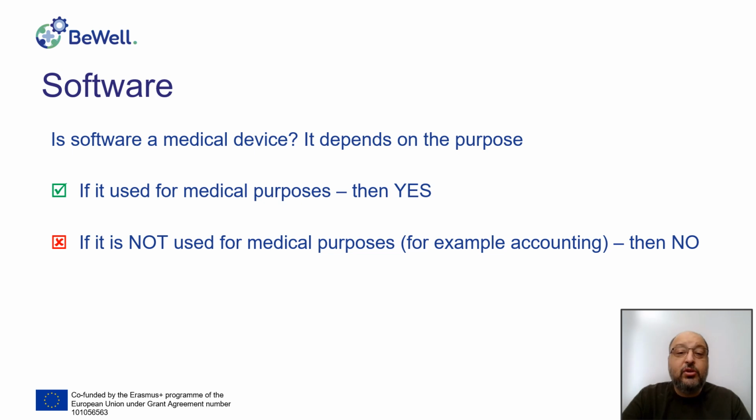One clarification in the regulation is that software that serves medical purposes is also a medical device. This refers to the purpose, not the location of the software. Accounting software used in a hospital is not a medical device.